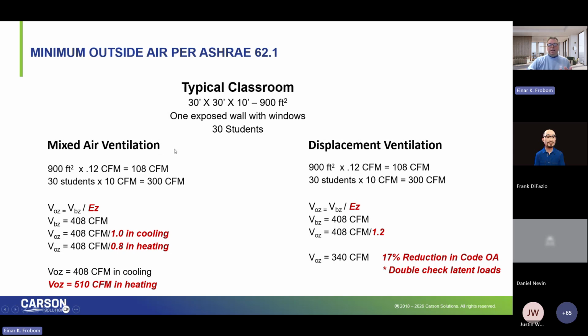So for comparison's sake, let's say you're evaluating, I really like DOAS and fan coil, or I want to investigate this DOAS and displacement induction thing. I've got a 10 classroom wing expansion going on, and I need to determine how much outside air I need to bring into each of those 10 classrooms. With a DOAS and a fan coil, I do the math on the students and the square footage, and then I apply this denominator, ventilation effectiveness. Cooling, it's a 1, heating, it's a 0.8, and the net result is that in heating, by code, I have to bring in 510 CFM of outside air to each classroom, times 10 classrooms in my example. That DOAS is 5,100 CFM.